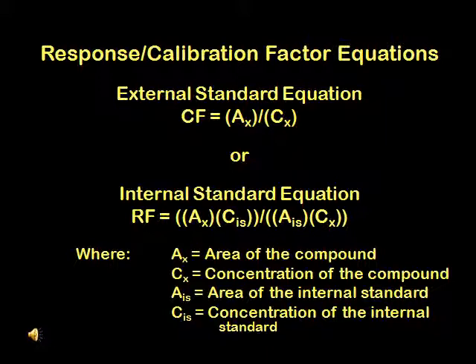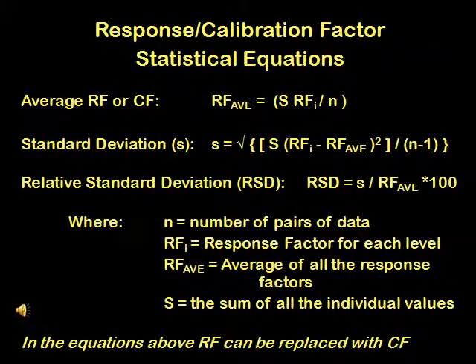When multiple internal standards are used in an analytical run, the method links individual internal standards to a group of compounds. However, the laboratory SOP must specify the internal standards to be used for which compounds.